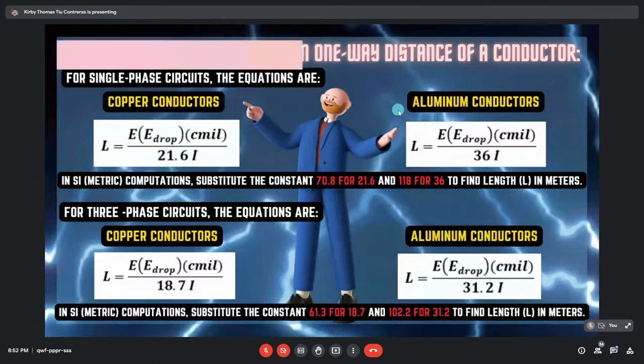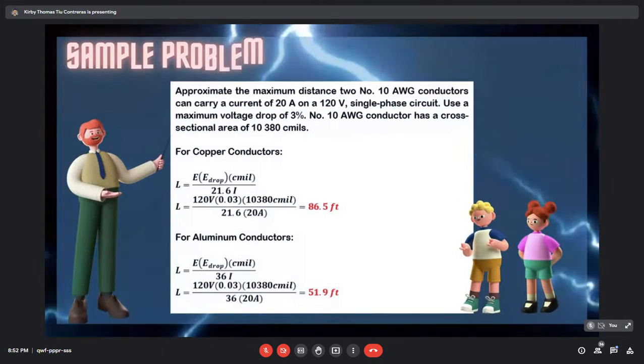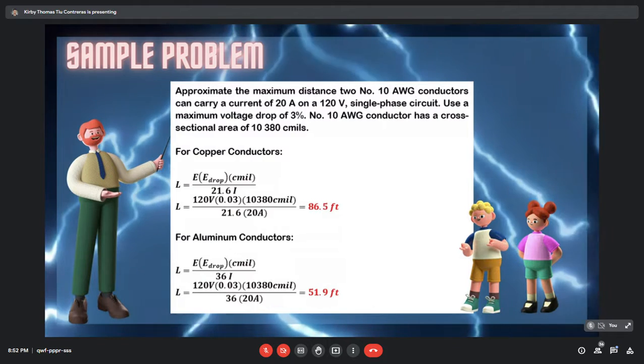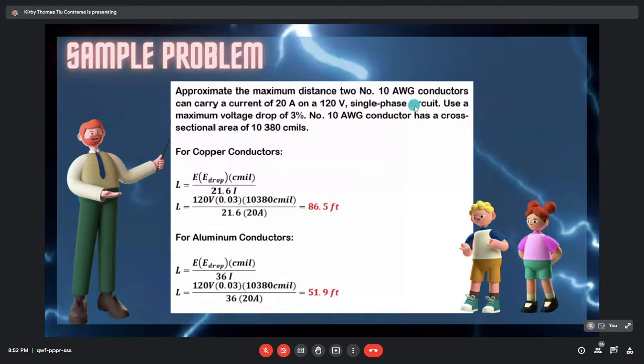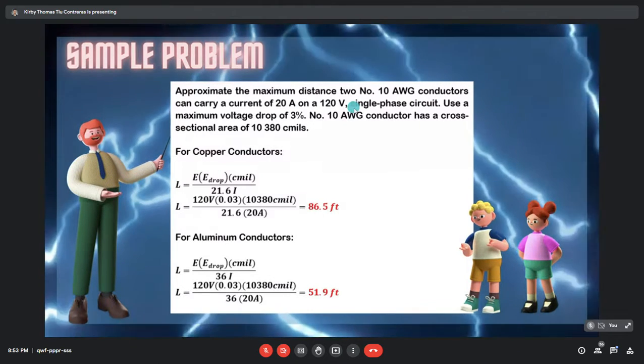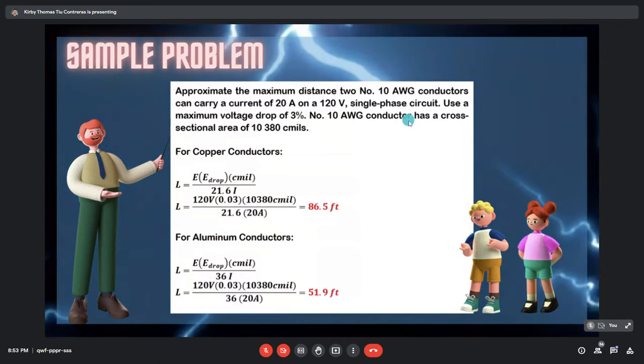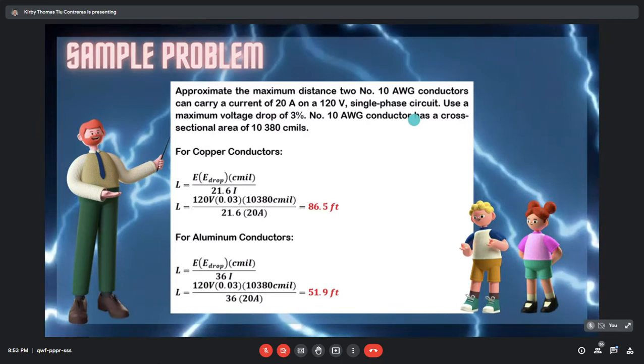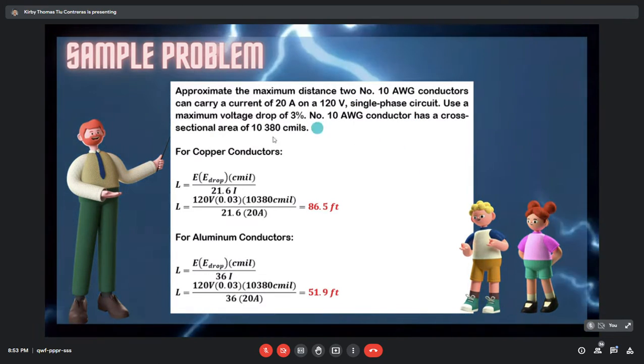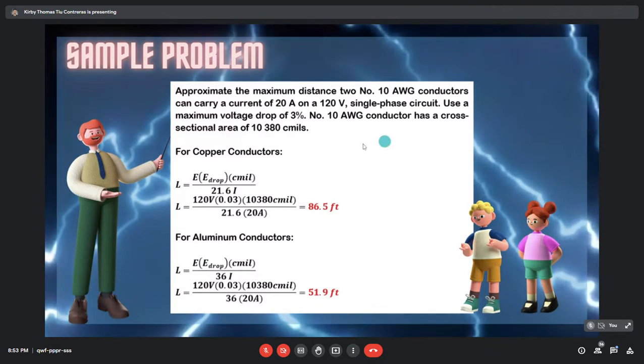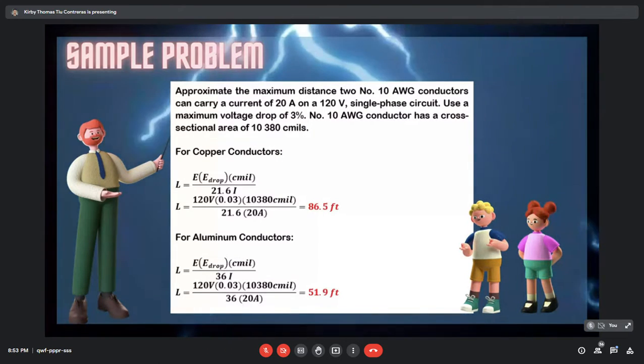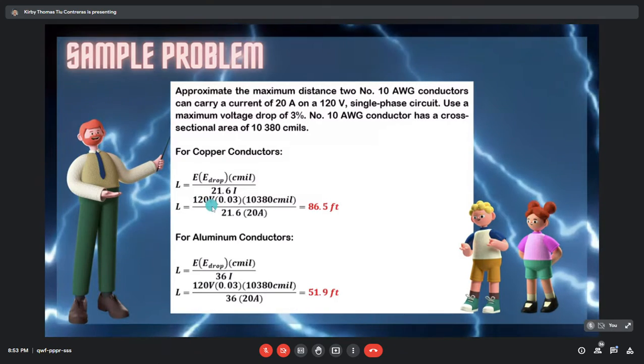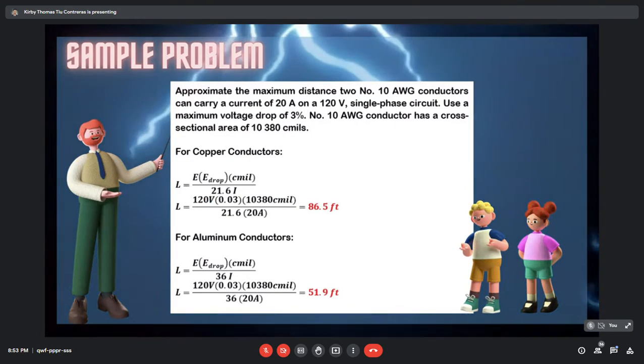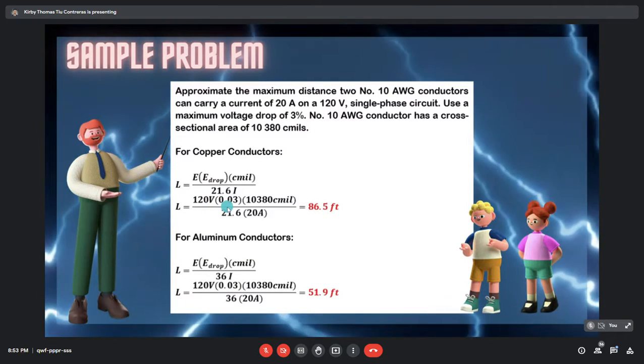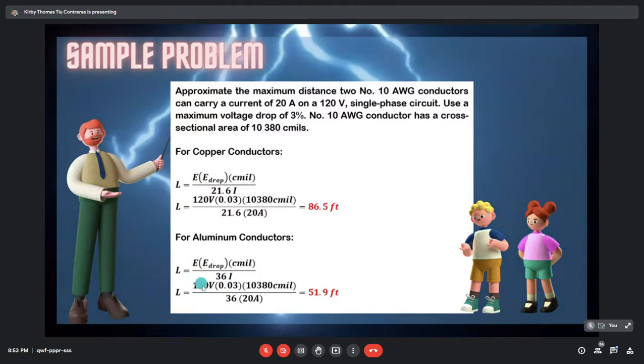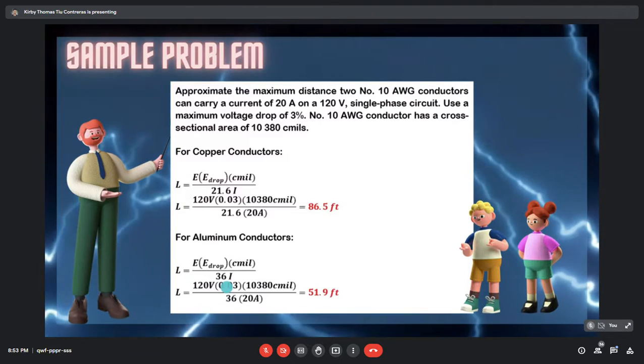So let's have another example. For getting the maximum distance of the conductor, we have: approximate the maximum distance of a number 10 AWG conductor that can carry a current of 20 amps on a 120 volts single phase circuit. Use a maximum voltage drop of 3%. A number 10 AWG conductor has a cross-sectional area of 10,380 circular mils. For the copper conductor, we have this formula. The 21.6 here is the resistance constant for copper conductors, whereas the 36 here is the resistance constant for aluminum conductors.